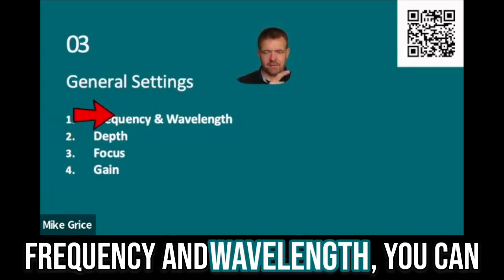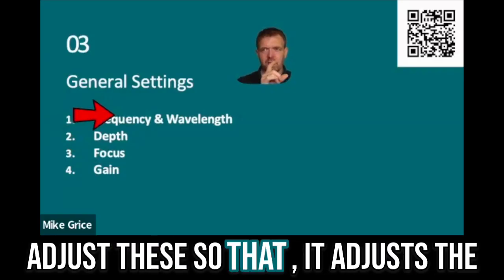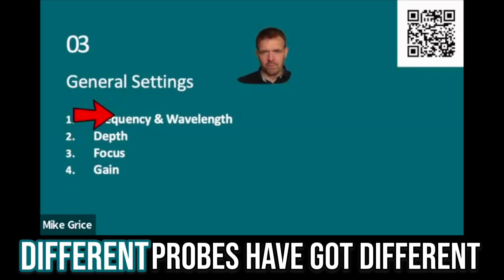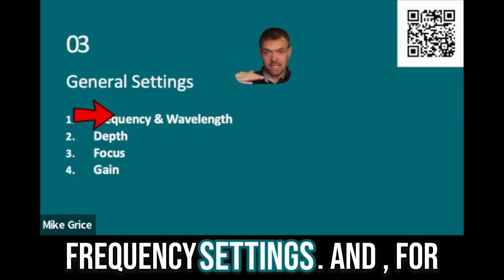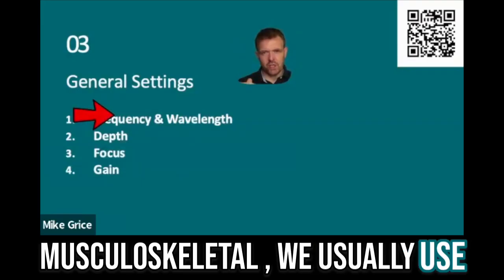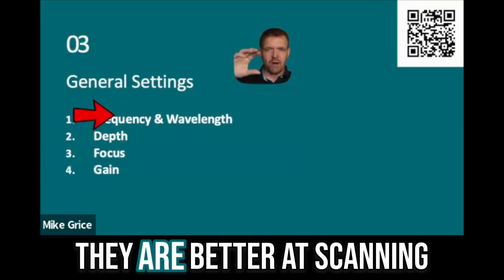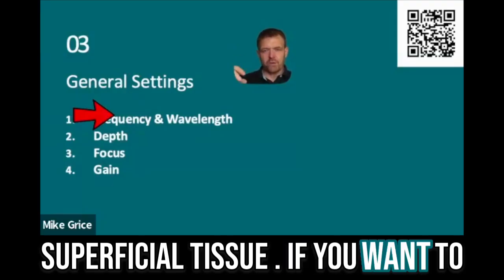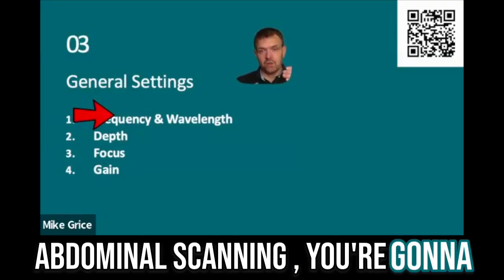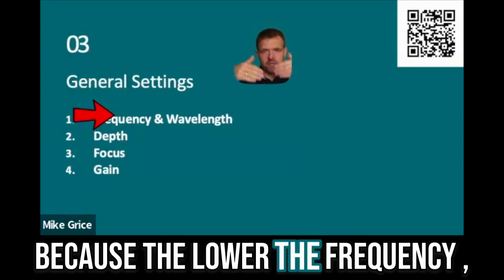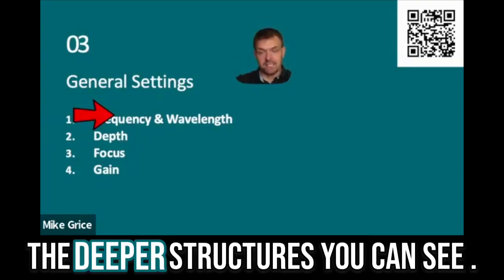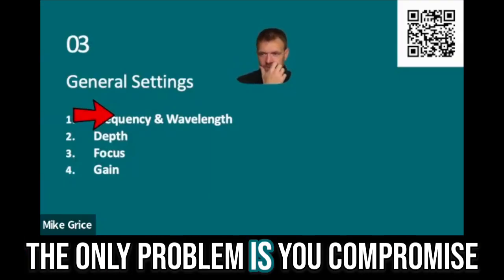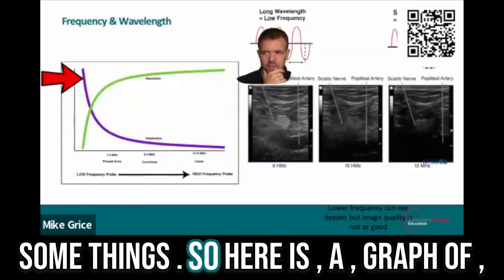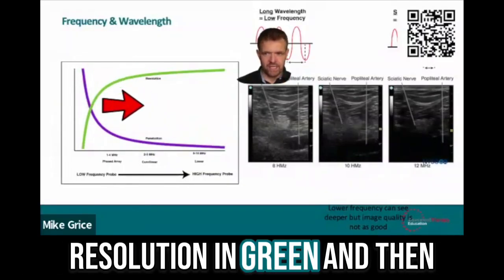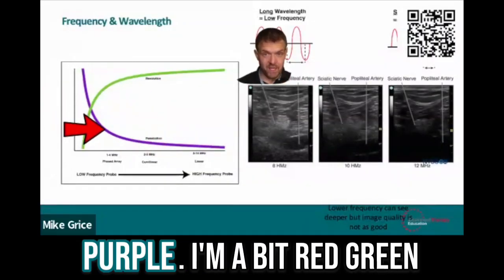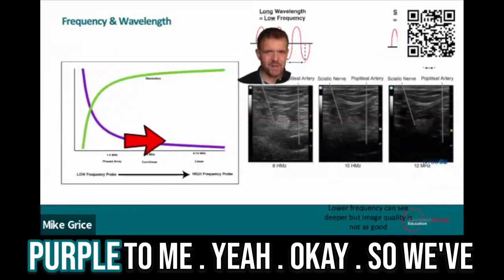So frequency and wavelength, you can adjust these so that it adjusts the settings on the probe. Now, different probes have got different frequency settings. And for musculoskeletal, we usually use higher frequency probes because they are better at scanning superficial tissue. If you want to scan viscera, so you want to do abdominal scanning, you're going to need a lower frequency probe because the lower the frequency, the better depth you can get and the deeper structures you can see. The only problem is you compromise some things. So here is a graph of resolution in green and then penetration depth in, I think that's purple. I'm a bit red-green colorblind, so I think that looks purple to me.